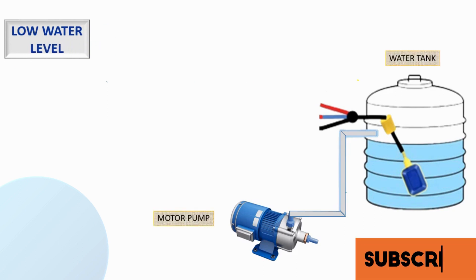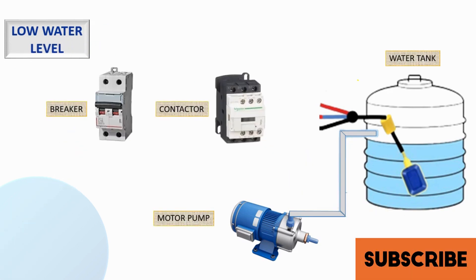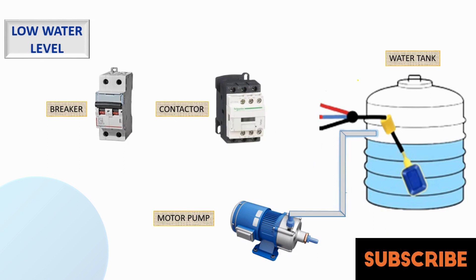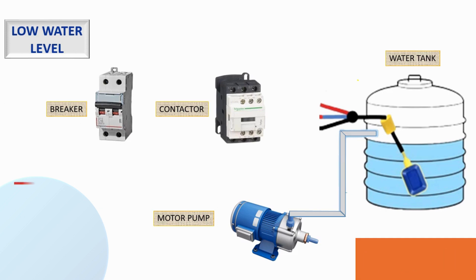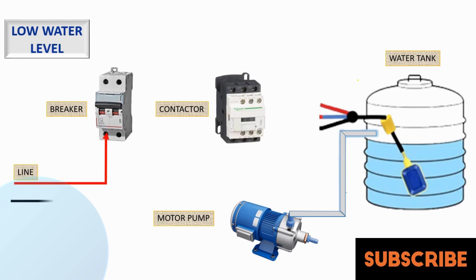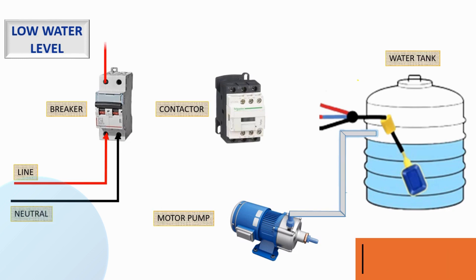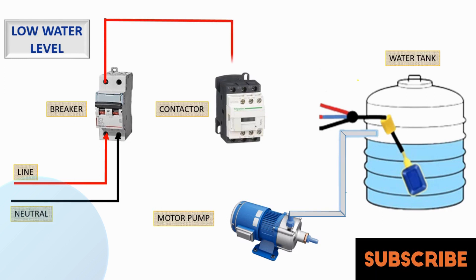Low water level — first action: When water levels drop to a predetermined low, the float switch triggers the control circuit. The control circuit activates the motor, ensuring water is pumped into the tank. This prevents the motor from running dry and safeguards the pump.